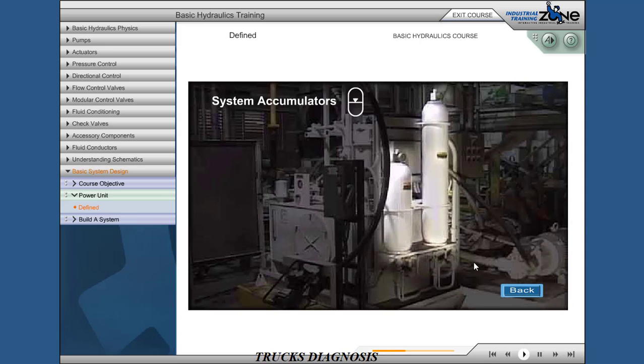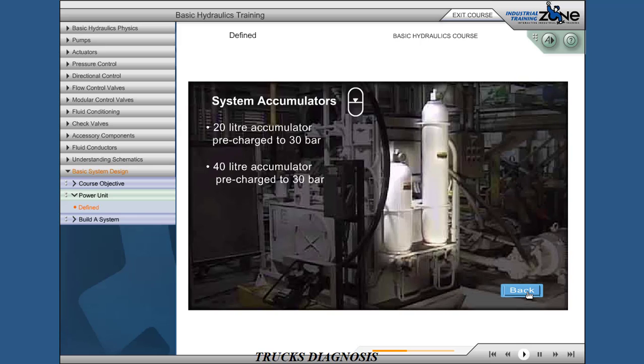System accumulators: 20 liter accumulator pre-charged to 30 bar, and 40 liter accumulator pre-charged to 30 bar. Provides stored energy in the event of input power loss.